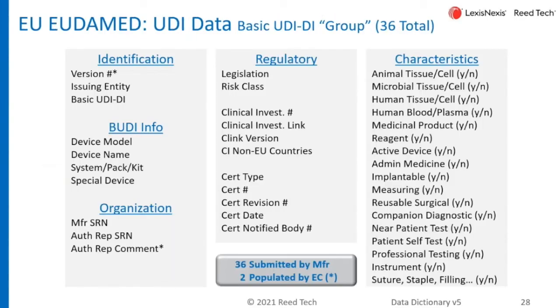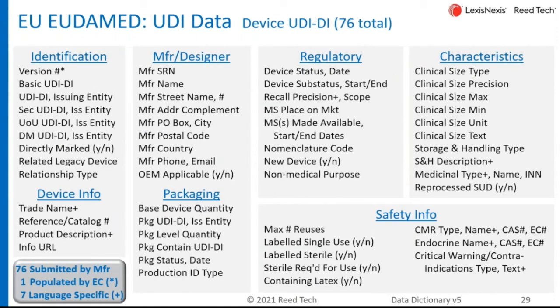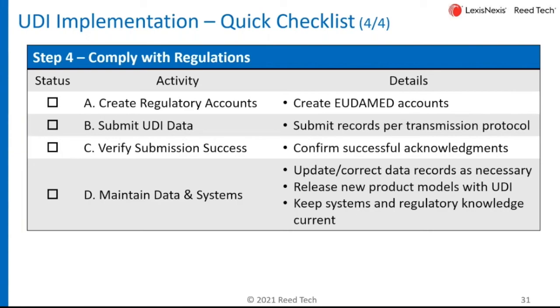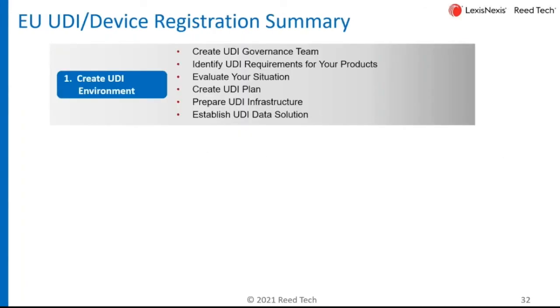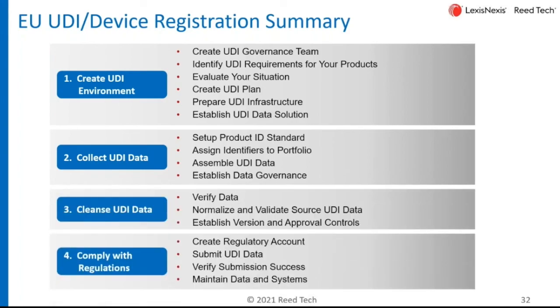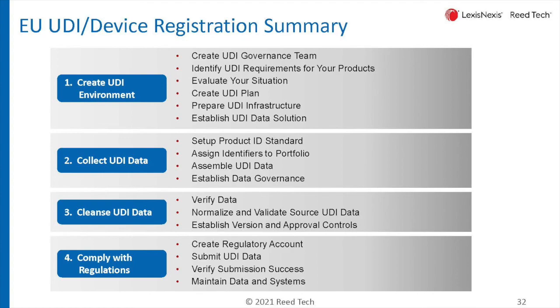There are 36 attributes relative to the basic UDI and 76 attributes specific to each device identifier, so it becomes quite a task to keep track of. Moving on to cleansing data — you need to verify data, normalize it, ensure it meets the regulations, and establish version controls. The last step is to comply with the regulations: create your regulatory accounts, submit the data, verify it's been submitted, and maintain the data over time. So those are the four C's — Create, Collect, Cleanse, and Comply.